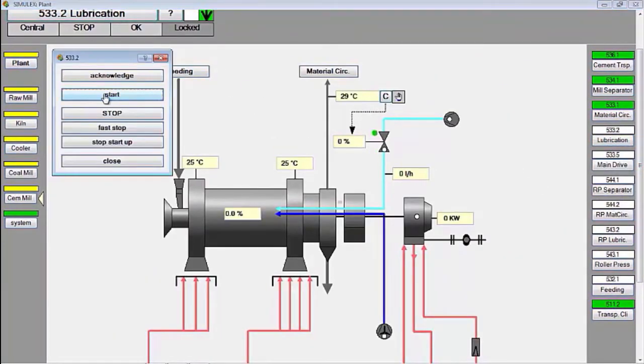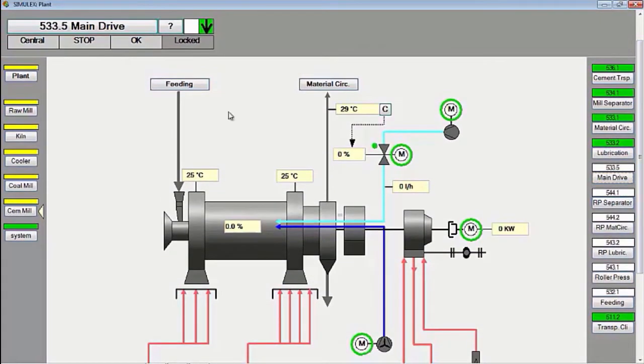Then we start mill lubrication to prepare to run the mill drive. Furthermore, start the mill drive. After the mill drive runs, we must immediately run the roller press group so that the mill is not empty for too long.